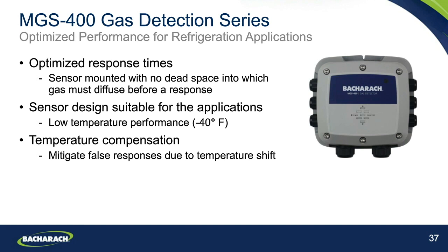Also important that the sensors are designed in a suitable way for the applications they're going into. And we have low temperature performance on the MGS-400 such that these can be installed and work effectively in environments down to -40 degrees Fahrenheit or -40 degrees C as well. Also important to note that the MGS-400 on all sensor types includes temperature compensation, and that can mitigate false responses due to changes in temperature, whether that be an ambient change or a process such as a defrost cycle. Many gas detectors out there using similar types of sensor technologies can generate a false response if there is a temperature shift, and this is mitigated and managed within the MGS-400 series by monitoring the sensor temperature and adjusting the outputs in accordance with how the sensor reacts under those temperature changes.